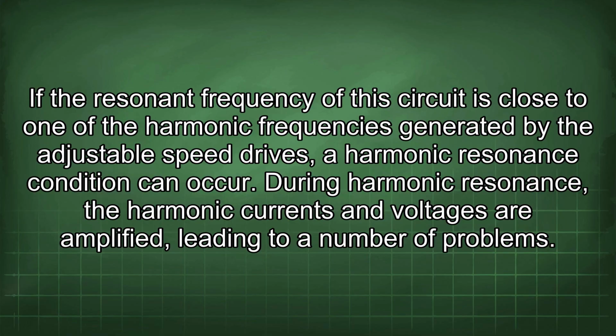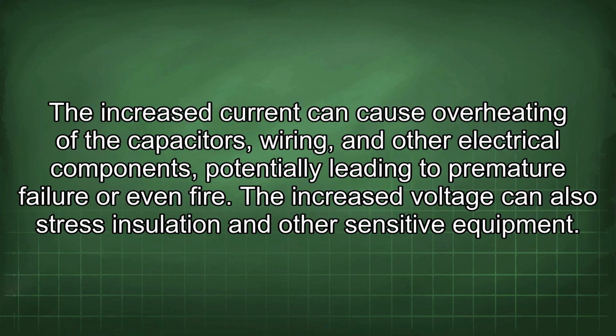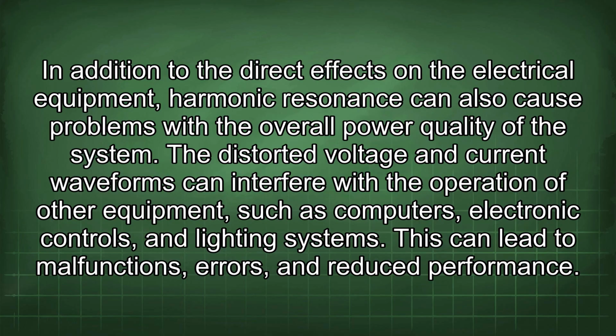During harmonic resonance, the harmonic currents and voltages are amplified, leading to a number of problems. The increased current can cause overheating of the capacitors, wiring, and other electrical components, potentially leading to premature failure or even fire. The increased voltage can also stress insulation and other sensitive equipment. In addition to the direct effects on the electrical equipment, harmonic resonance can also cause problems with the overall power quality of the system. The distorted voltage and current waveforms can interfere with the operation of other equipment, such as computers, electronic controls, and lighting systems. This can lead to malfunctions, errors, and reduced performance.